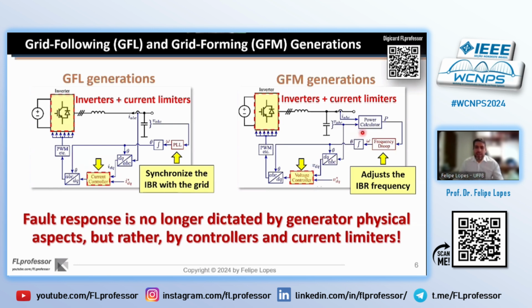And something like, they do not estimate the frequency, but they calculate the frequency for a given active power at its output. And so here we may have some impacts on these outputs, depending on how you implement such a frequency droop. But the main problem in this case, although these generations will be able to form grids, is still the presence of inverters which require the limitation of currents.